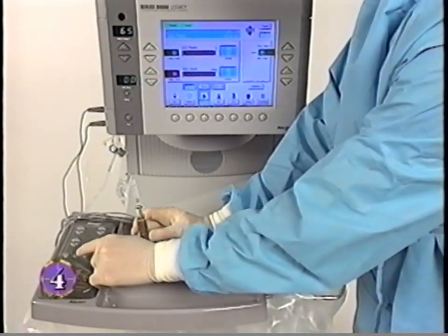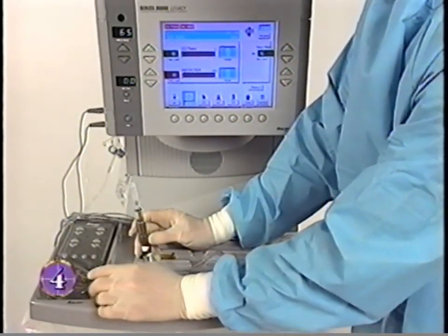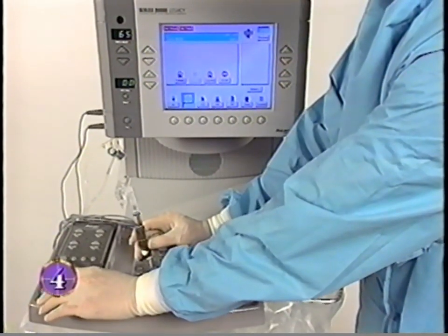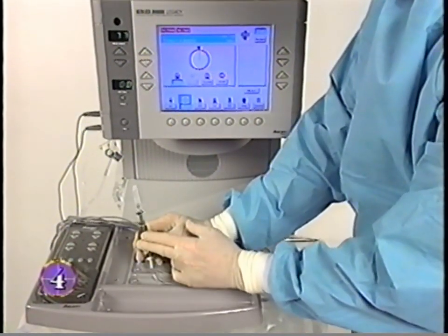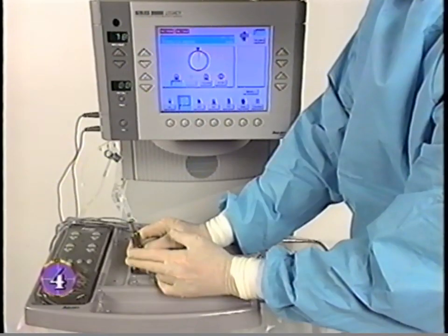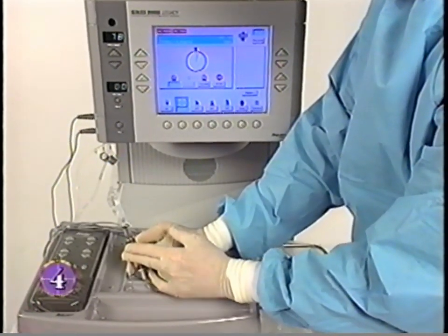Push the hydro mode button, then press the test button. Holding the handpiece vertically, select Prime to activate the injector priming sequence. Be sure to tap the handpiece during this sequence.